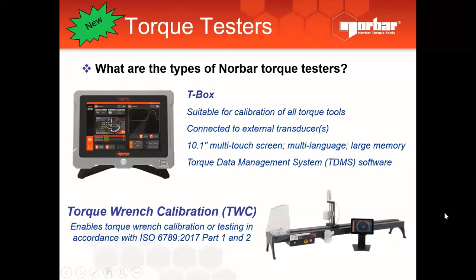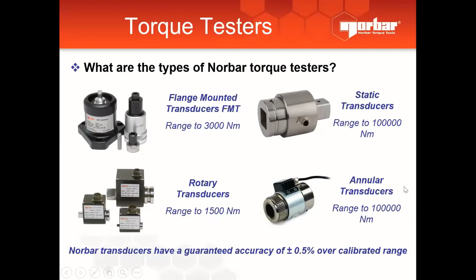So what are the types of Norbar torque tester that we have? This is a transducer. Norbar transducers are all 0.5% accuracy or better, or 0.25. These are more in-depth for calibration, so I won't go too deep. To let you know, transducers have 4 various types: flange mounted transducer, static transducer, rotary transducer, and annular transducer. Measuring torque and angle is only available on rotary and annular transducers.